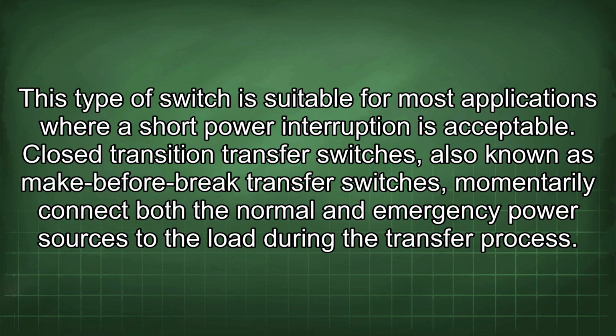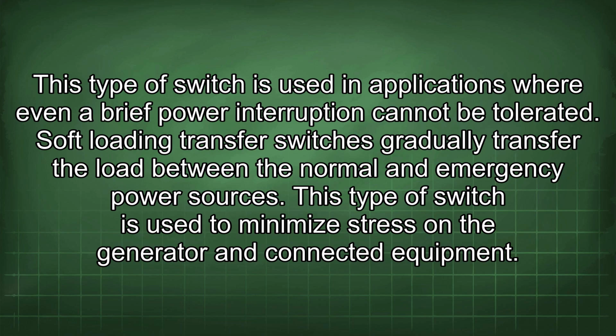Closed transition transfer switches, also known as make before break transfer switches, momentarily connect both the normal and emergency power sources to the load during the transfer process. This type of switch is used in applications where even a brief power interruption cannot be tolerated. Soft loading transfer switches gradually transfer the load between the normal and emergency power sources. This type of switch is used to minimize stress on the generator and connected equipment.